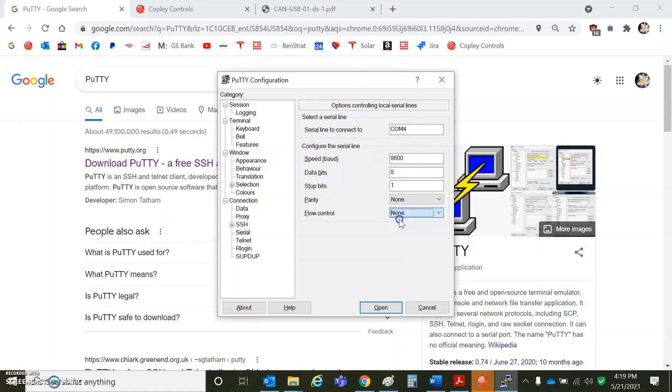Turn that off — set to none, standard 8N1 — and we should be able to open up the COM port to the drive. I've got it connected to the drive and the power's turned on. I'm going to do 'get from RAM 0x24', and that tells me the mode of operation of the drive.